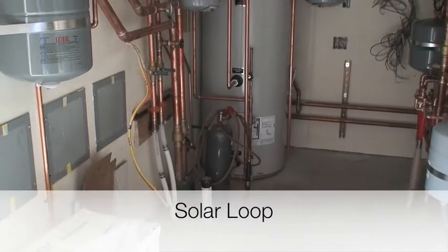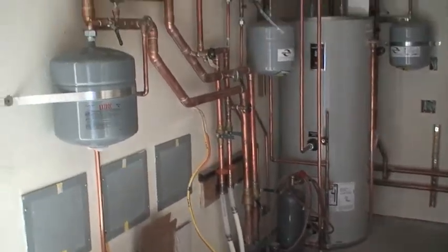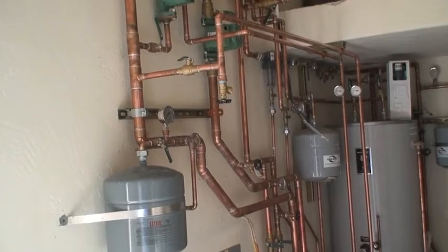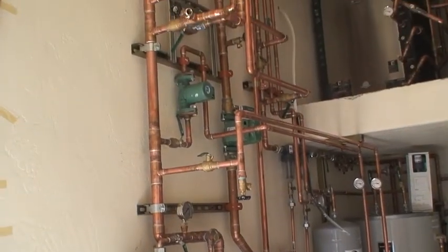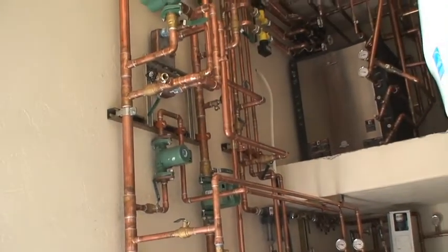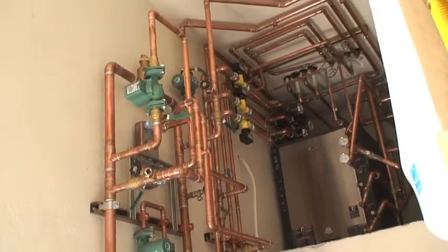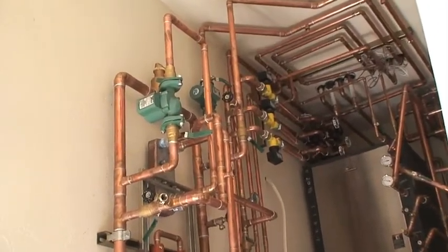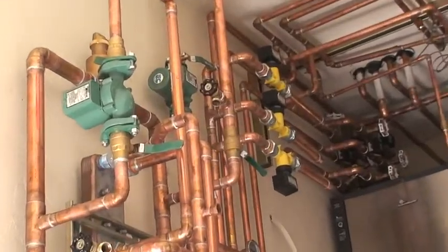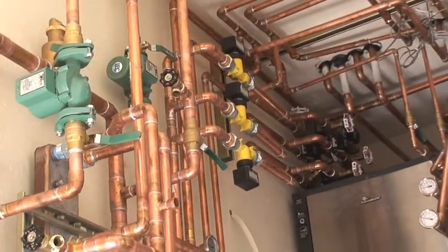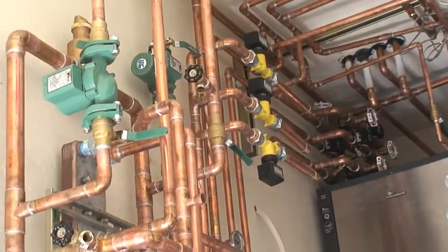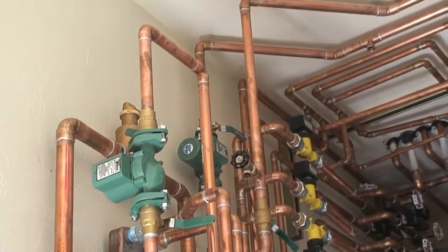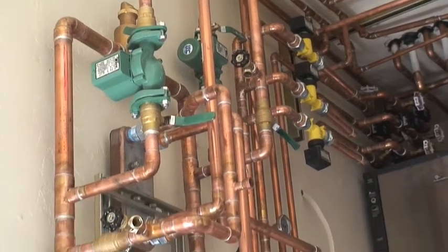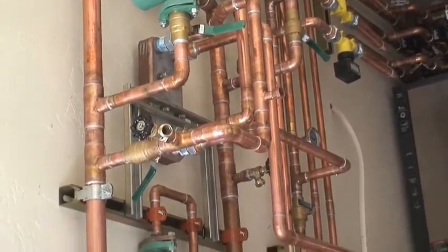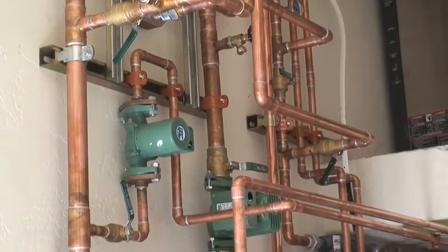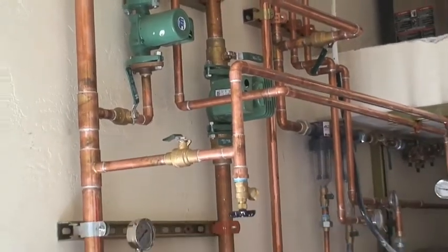Here is where the life of the home pretty much lives. This is the solar loop, a feed loop with 1.5 inch copper pipe pulling heat out of an exchanger that's outside in a different building, supplying heat to various things in the house. We're supplying hot water for a hot water maker, for geothermal, for the radiant floor, and also a boost on the geothermal heating and cooling units.